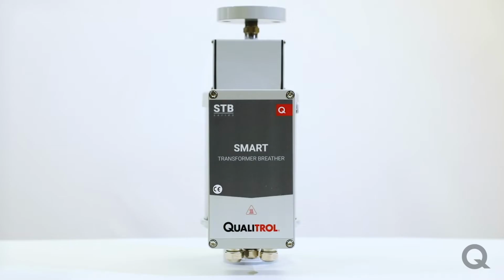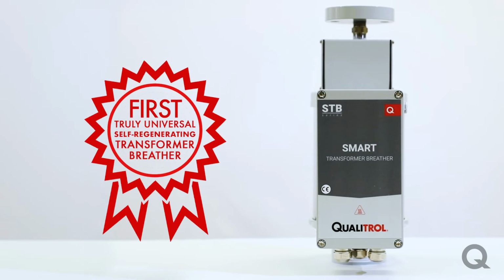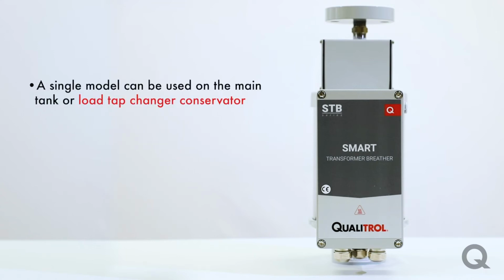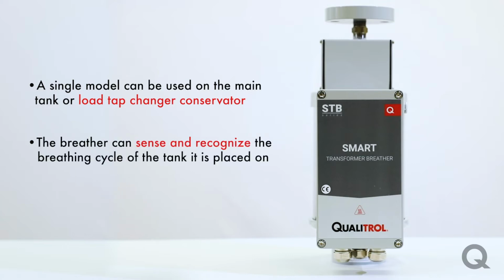So on the topic of smart breathers, Qualitrol is proud to be offering the first truly universal self-regenerating transformer breather. With this next generation of breathers, a single model can be used on either the main tank or load tap changer conservator. This is done by the breather's ability to sense and recognize the breathing cycle of the tank it is placed on. Our new breather is also fully configurable, so this means you can pick and choose the features that you need and want.